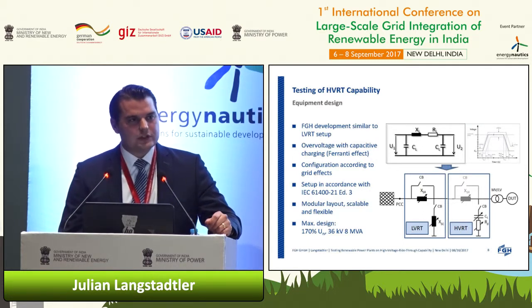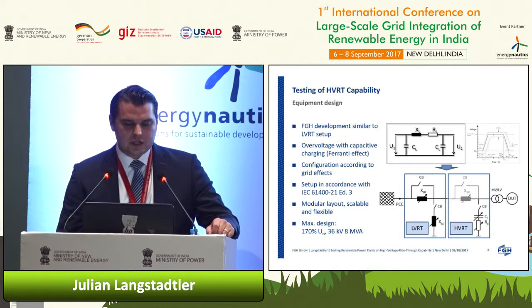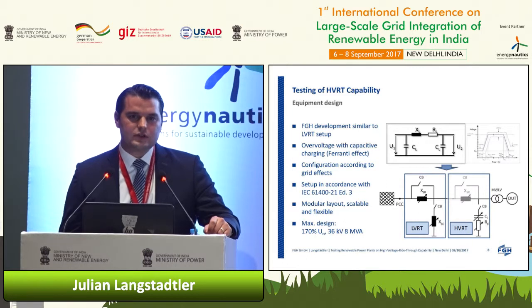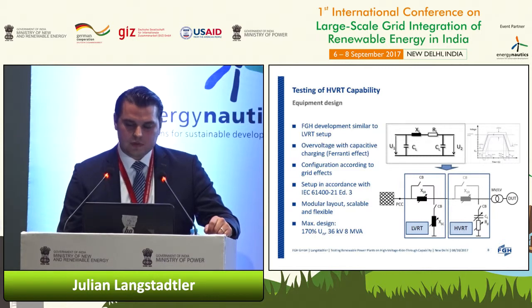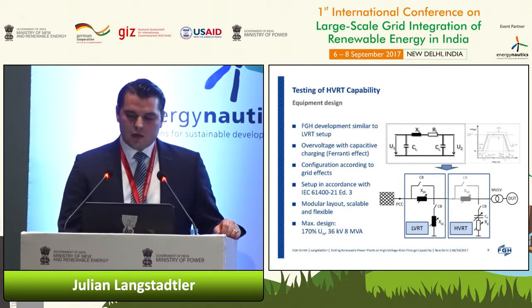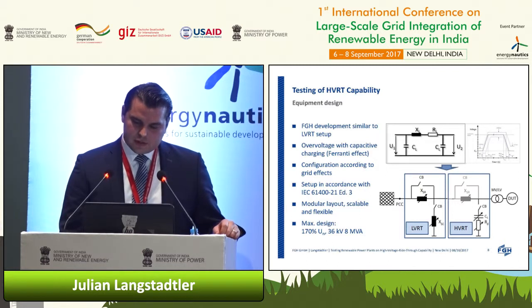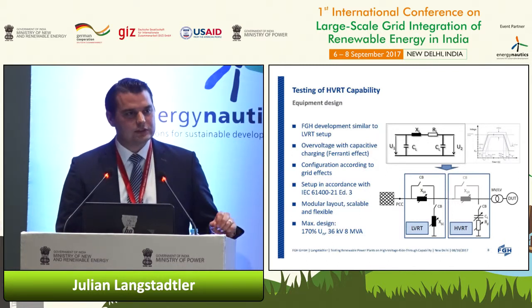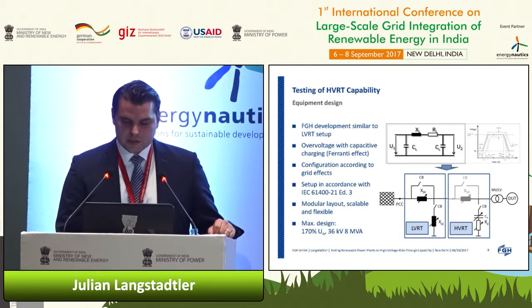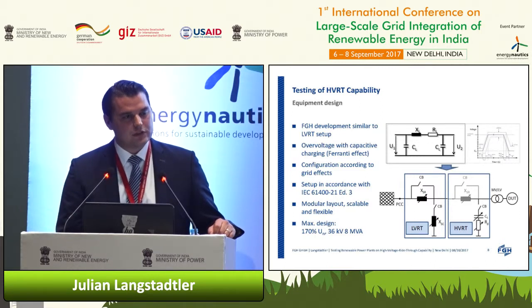And FGH developed a setup which is quite similar to the LVRT setup. And it is based on the Ferranti effect, where you have overvoltage with capacitive charging. And this is actually also what happens in the grid when the overvoltage occurs. Here you can see an equivalent diagram of a transmission line, where in the horizontal path you have the inductance and the resistance, whereas in the vertical path you have capacitors. And when there's a short circuit, you will have a connection here at the end, and only the inductance is visible. So that means for the LVRT equipment or testing procedure, you have an inductive voltage divider.